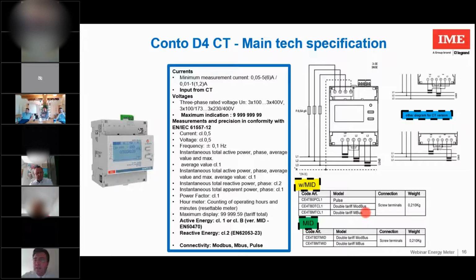Does the meter have phase sequence detection to avoid wrong connection? No, but there is the phase angle for the current and the voltages. So you have only to check the phase angle of the voltages. If you have less or more than 120 degrees between one phase and the other, there is a wrong connection. So it's very simple. There isn't an error, but there is a more specific parameter. So it's also easier to find the error with the angle distortion.